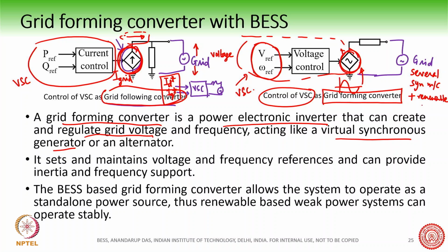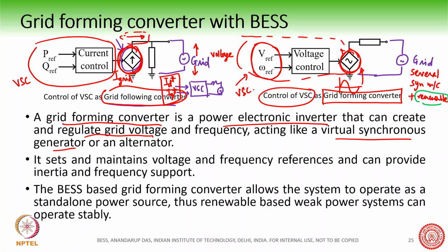Now if the percentage of renewable is high, if this percentage of renewable is going up and up, then synchronous machine percentage is going down. So what happens is that the grid will start to behave as a weak grid, or sometimes as a microgrid. So then the voltage and frequency will start to vary a lot. There, this grid forming converter starts to play a very important role, because it acts as a controllable synchronous machine inside the grid.